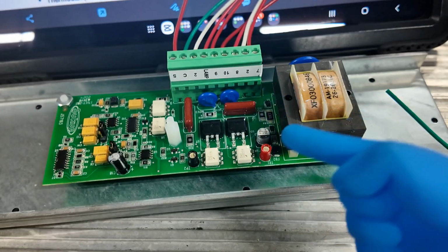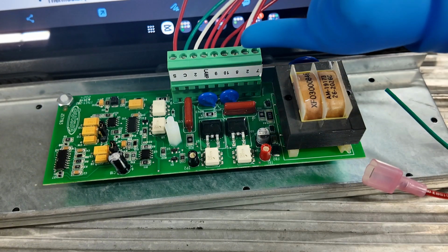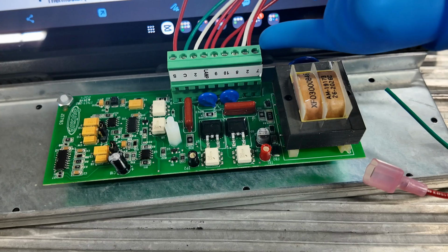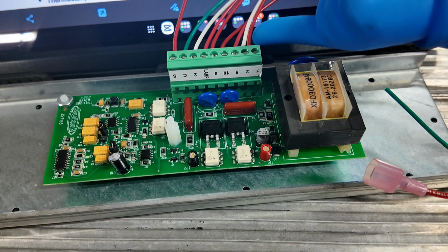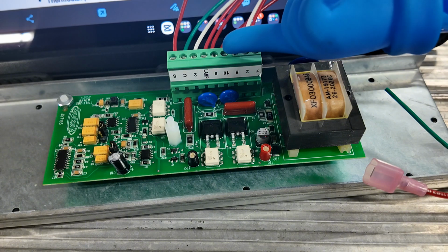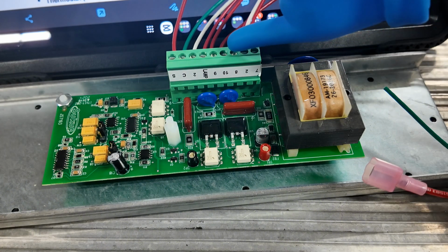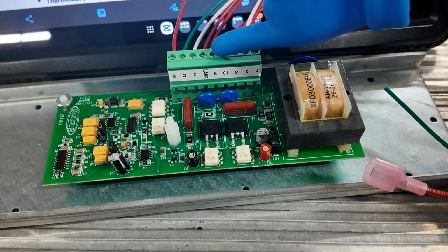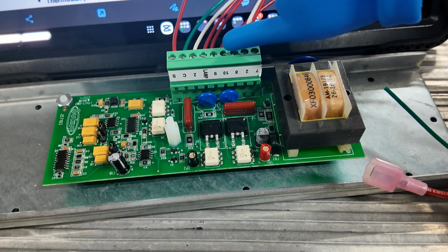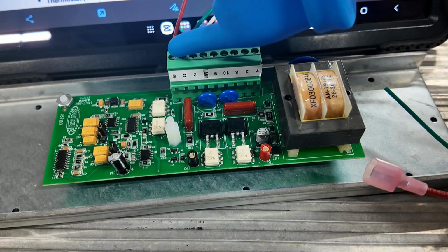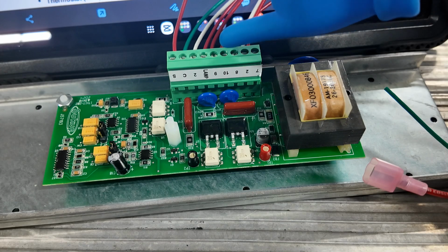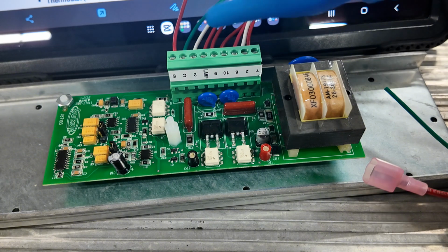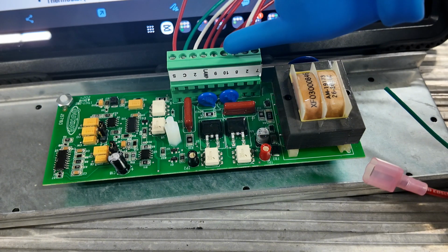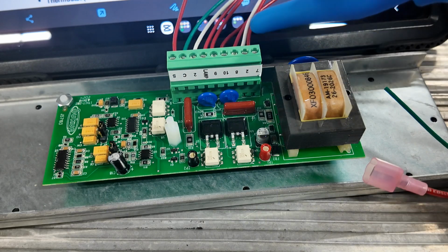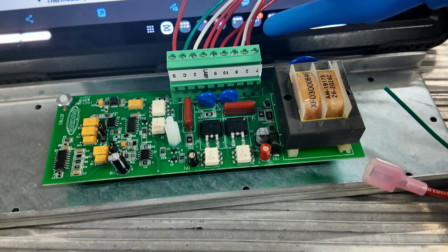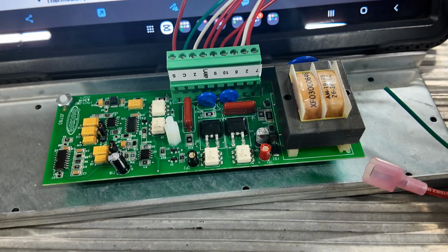Now, this board here works the same as most flame rectification boards. When you put electric on 7 and 8, it waits a preset amount of time, about 20 seconds, and then it puts 110 voltage out 9 and 10. After a preset amount of time for ignition, number 9 turns off, and 10, if it starts sensing flame on S, it will leave 10 on so the burner continues to run. If it does not sense flame, it will turn off the burner and lock out. To retry the burner, you turn the power switch off and back on, which turns power off to 7 and 8, and it retries.